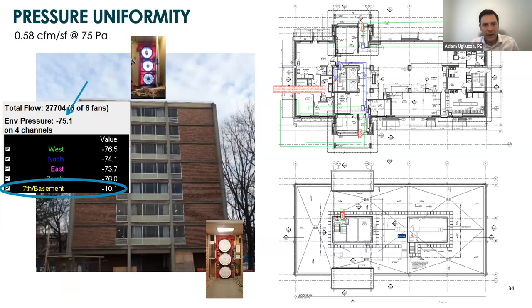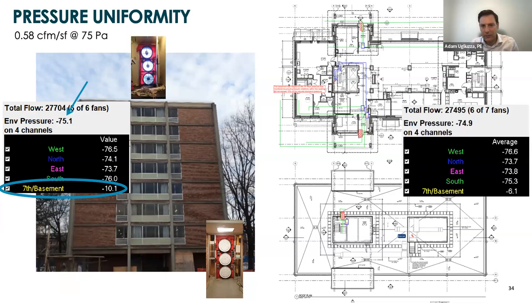I moved the fan up to the top of the building, and then we were able to have a successful test. So that'll happen. You might experience that on a project where you're not getting uniformity. It's important that the testing agency is checking for uniformity as well. So there's something to keep an eye out for. That's the intent for the test. That's how you're supposed to run it and get a properly run test.